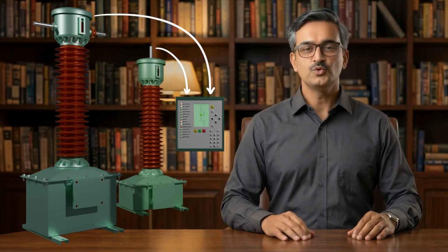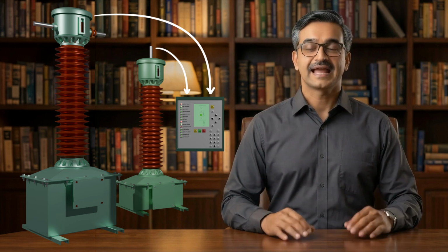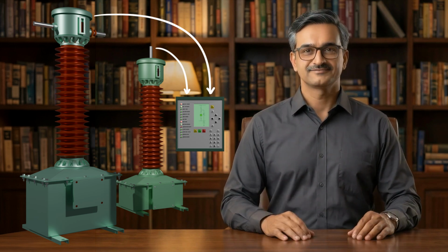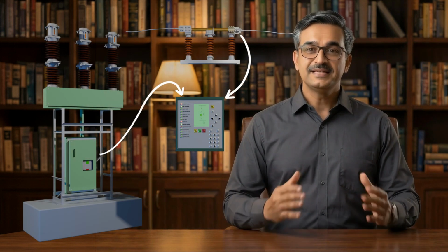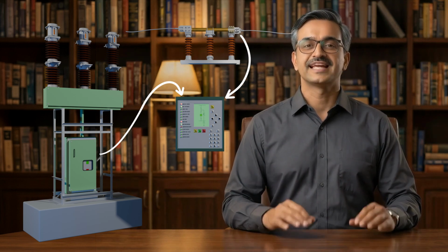So, the BCU has dedicated input terminals that directly receive current inputs and voltage inputs from the current transformers and voltage transformers respectively. Next, the BCU also receives analog inputs through transducers for different analog quantities like temperature, tap position, and similar parameters. Further, for monitoring the status of different auxiliary contacts of circuit breakers and isolators, the BCU uses binary input terminals with potential free contacts of the equipment.